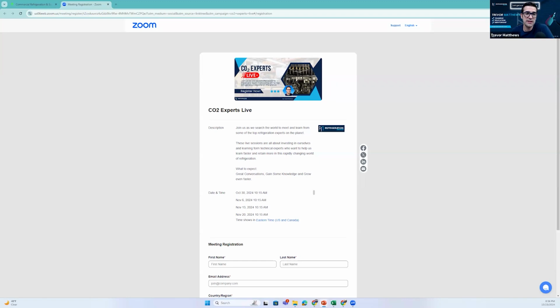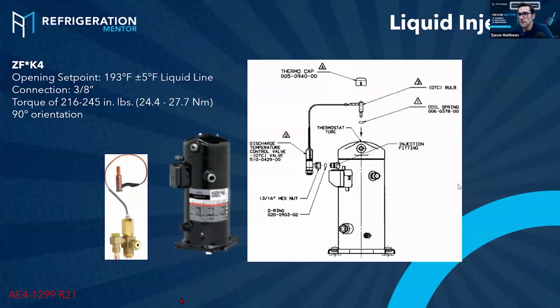It would be just, it looks like a TX valve. That's what it looks like. And let me find one here. Yeah, liquid injection here. Let's take a look at this one right quick. So this is kind of the liquid injection for the Copeland scrolls. There's lots of different ones. It goes right into the head. There's a little spring on there right here. Make sure that spring's on there. If it's not, it's going to trip off.